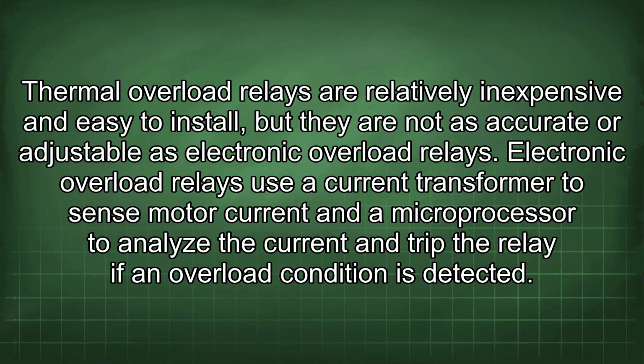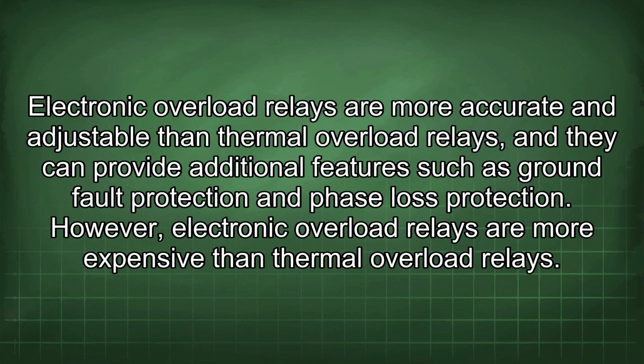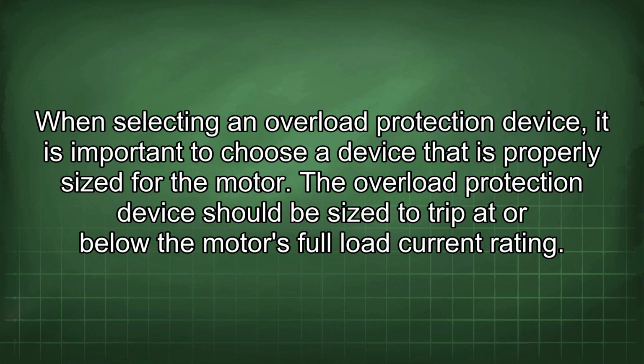Thermal overload relays are relatively inexpensive and easy to install, but they are not as accurate or adjustable as electronic overload relays. Electronic overload relays use a current transformer to sense motor current and a microprocessor to analyze the current and trip the relay if an overload condition is detected. Electronic overload relays are more accurate and adjustable than thermal overload relays, and they can provide additional features such as ground fault protection and phase loss protection. However, electronic overload relays are more expensive than thermal overload relays. When selecting an overload protection device, it is important to choose a device that is properly sized for the motor.